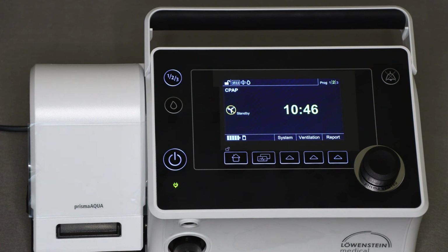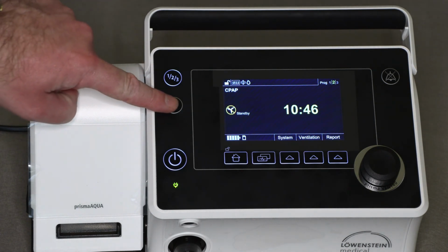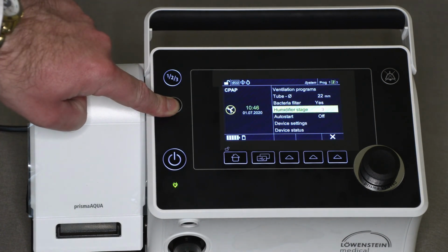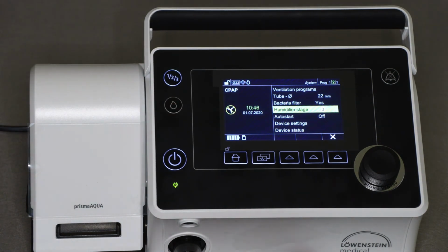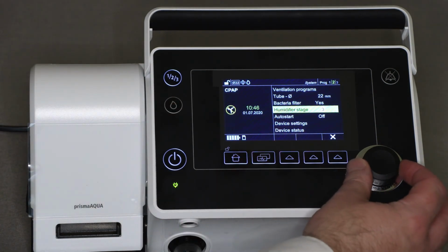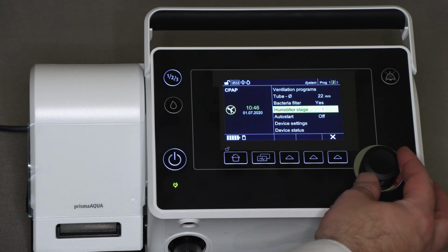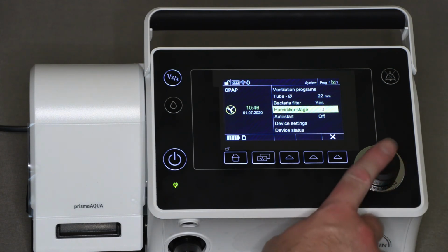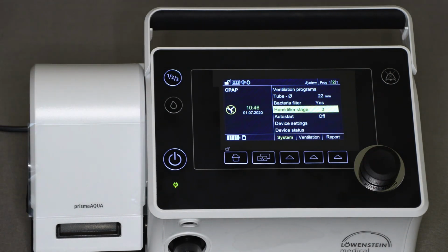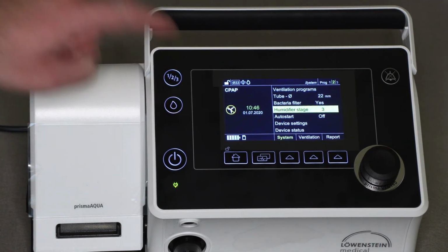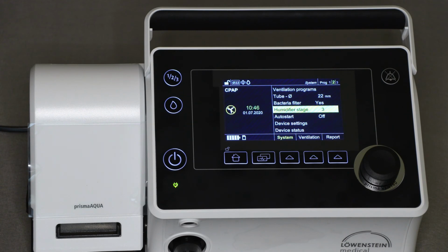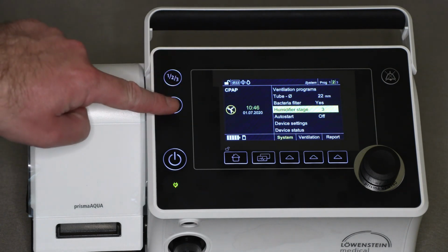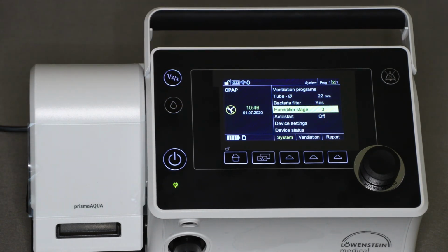Once attached, prismaVENT will automatically heat the water inside Prisma Aqua when therapy is started, and water vapour will be mixed with the airflow from the outlet at the front of the ventilator and passed on to the user through the breathing tube. To adjust the setting for heat, press the humidifier button, which will direct you straight towards the setting for adjusting the humidifier. The heat setting can be adjusted in 6 stages, setting 1 being the coolest. If the humidifier button is lit up, it means the humidifier is turned off and won't heat the water. Press and release the humidifier button once to turn the heater for the humidifier on.